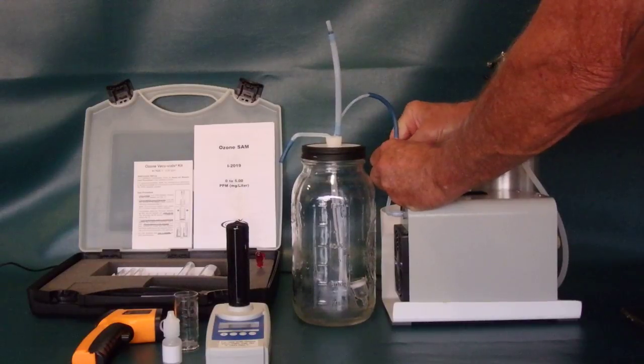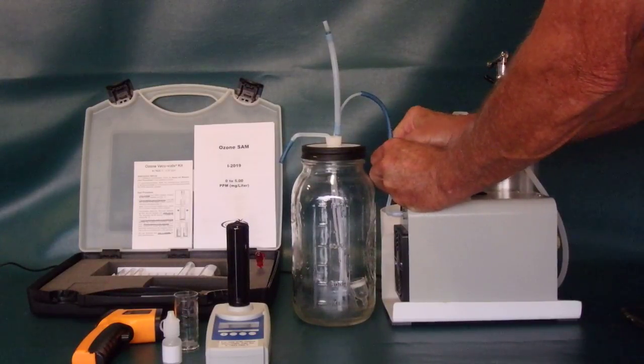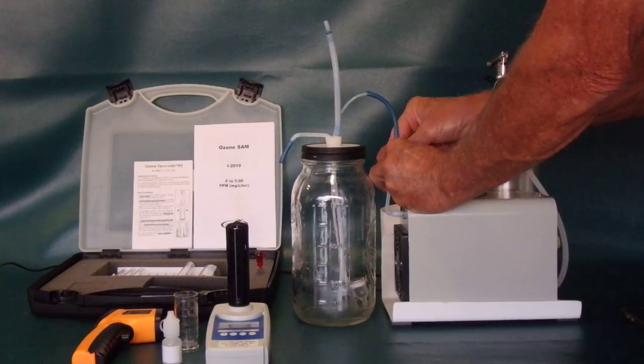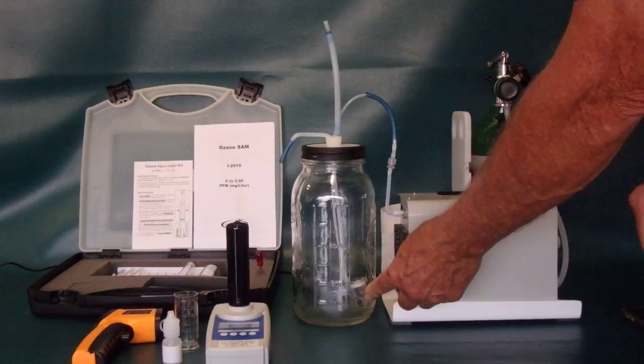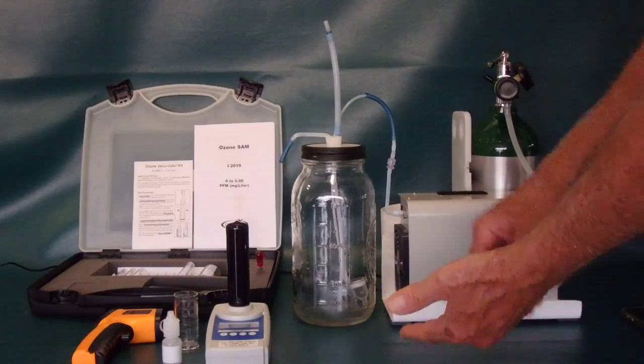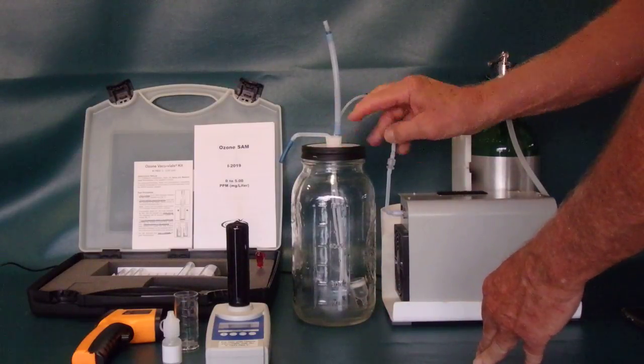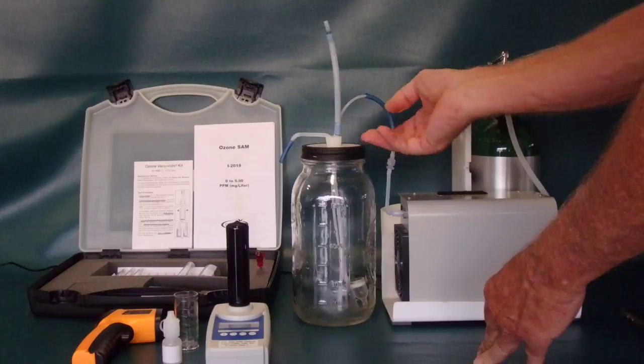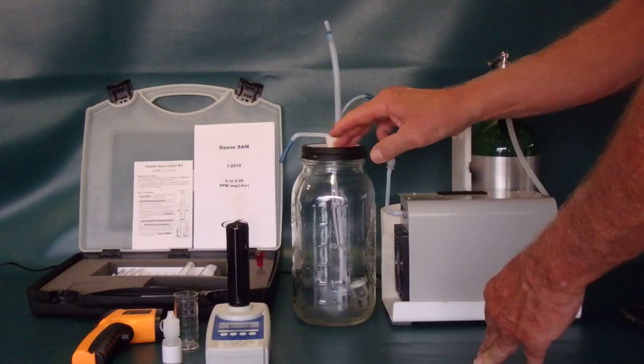The unique thing about this system is it's all glass, including the inside of the glass diffuser, Teflon tubing. Teflon and glass are the only materials impervious to ozone. A Teflon lid is connected by a metal clamp but that does not touch the water or the ozone at all.